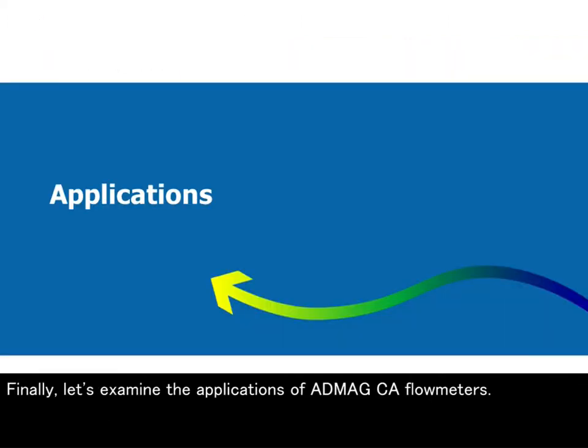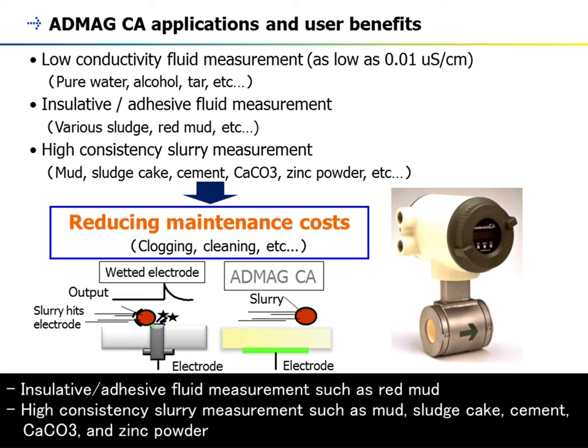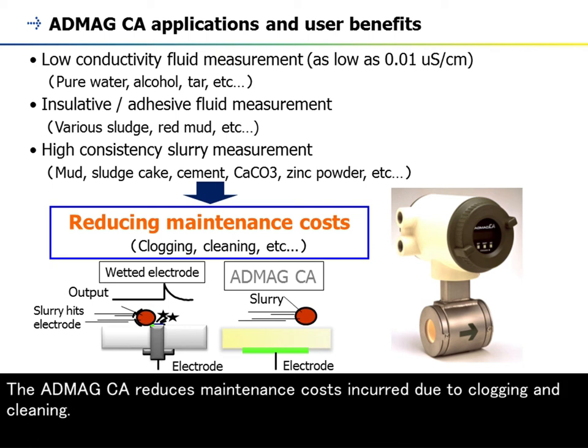Finally, let's examine the applications of ADMAG CA flow meters. The ADMAG CA flow meter can be used for the following applications: low-conductivity fluid measurements such as pure water, alcohol, and tar, with conductivity more than 0.01 microsiemens per centimeter; insulative or adhesive fluid measurements such as red mud; and high-consistency slurry measurements such as mud, sludge cake, cement, CaCO3, and zinc powder. The ADMAG CA reduces maintenance costs incurred due to clogging and cleaning.